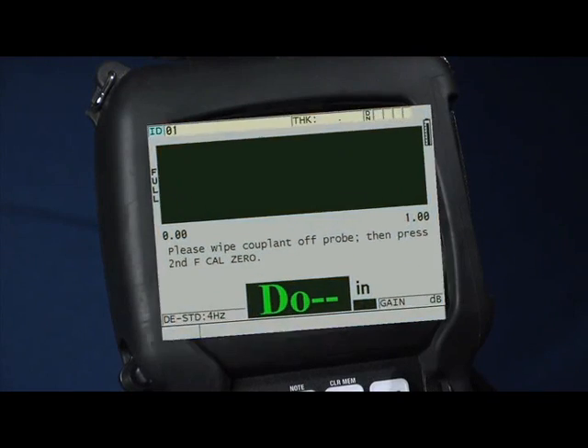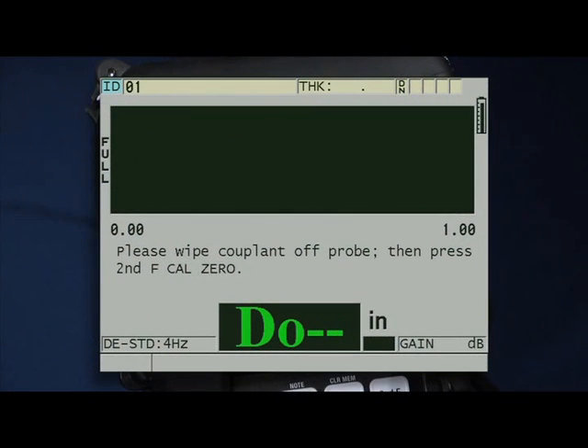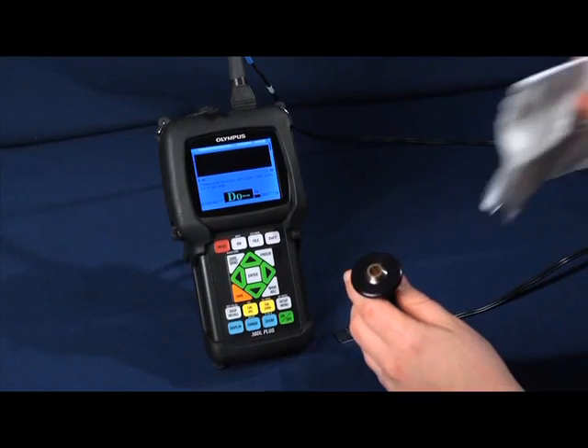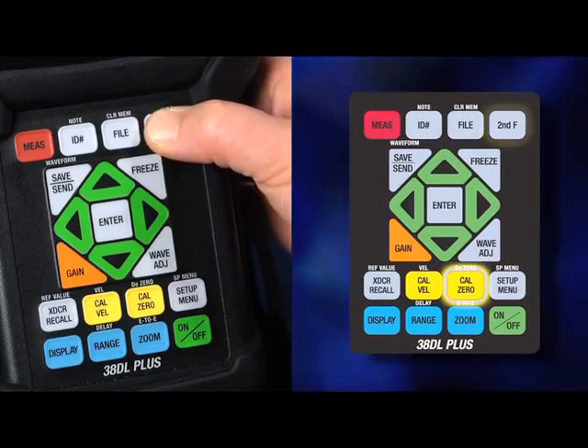To start, simply plug in any D790X series transducer. The gauge will prompt us to perform a do zero. This is done by wiping the couplant off the tip of the probe, then pressing the second function and the cal zero button.